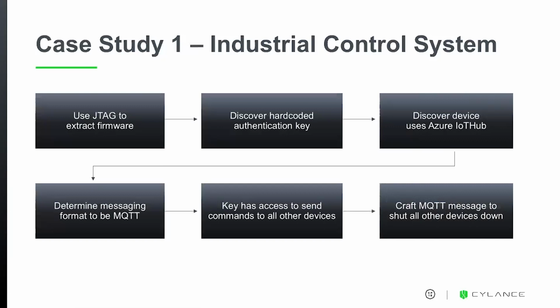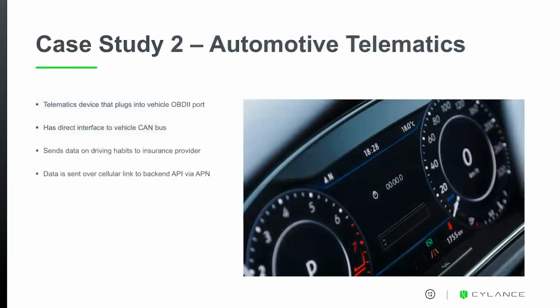The other thing that we found was that it was also possible to delete devices. Through a bit of interesting behavior, we found that once you deleted devices, it was very difficult to get them back in also. So that's just an example of an attacker who obtains one of these devices, extracts that key, and does their homework, and can then cause a fairly significant denial of service against thousands of systems that monitor data centers.